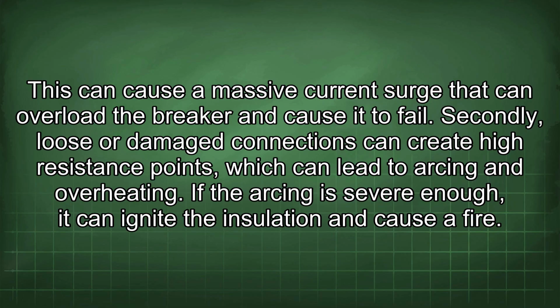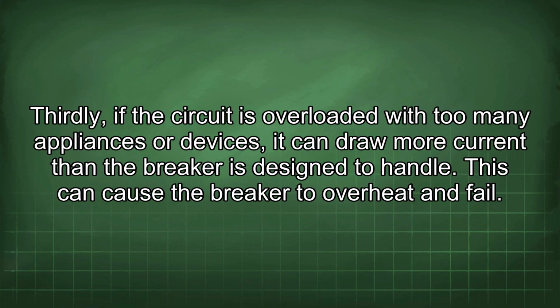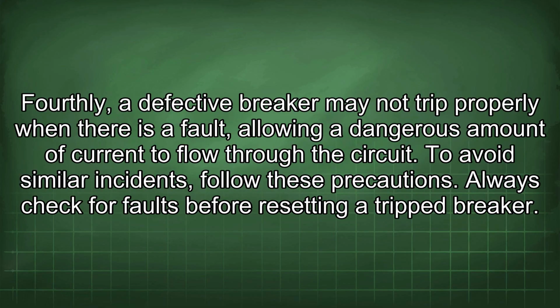Secondly, loose or damaged connections can create high resistance points which can lead to arcing and overheating. If the arcing is severe enough, it can ignite the insulation and cause a fire. Thirdly, if the circuit is overloaded with too many appliances or devices, it can draw more current than the breaker is designed to handle. This can cause the breaker to overheat and fail. Fourthly, a defective breaker may not trip properly when there is a fault, allowing a dangerous amount of current to flow through the circuit. To avoid similar incidents, follow these precautions.